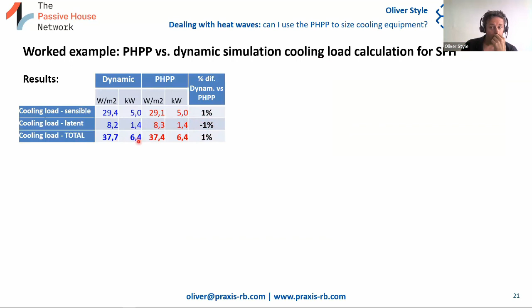If we look at a zone by zone level, we start to see some differences. If we apply 37.4 watts per square meter to each zone in the PHPP, these are the red bars here. If we look at the dynamic calculation, which varies zone to zone taking into account equipment gains, occupancy, and solar radiation, we see a big difference. This is a small example, but extrapolated to a larger building you can start to get problems. The peak cooling load for the kitchen, according to the dynamic model, is 37% higher than according to our PHPP.